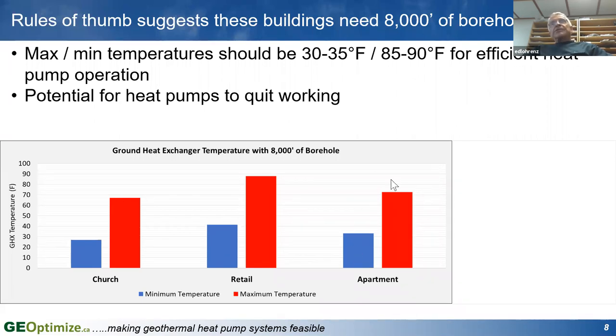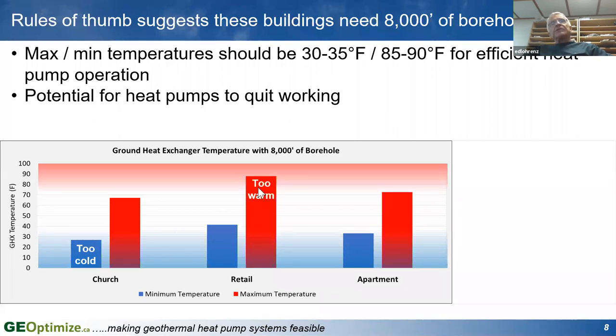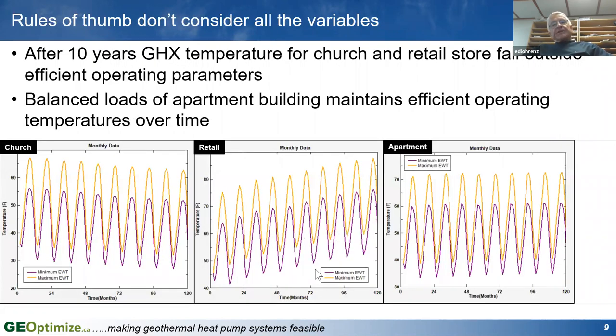Again, the temperatures in the ground heat exchanger in the apartment building are somewhere in between. So what happens is that this one is going to get too cold to operate very efficiently. This one's going to get too warm to operate very efficiently. And just like baby bear, this one's just about right. So what that means on the temperatures that the heat pumps are going to see over time, and this is about a 10-year period, in the church the temperature of the ground heat exchanger is going to gradually deteriorate where it's going to get too cold. And that can happen over 5 or 10 or 15 years. Retail store, exactly the opposite. Meanwhile, the apartment building is going to run happily forever.